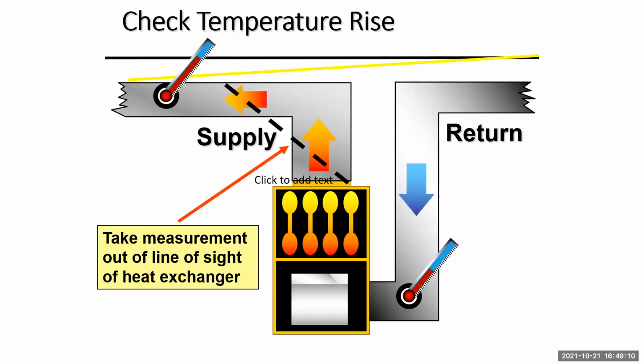Temperature rise. This is critical. If you guys call us and you're having problems, we're going to ask your temperature rise. That and static pressure, and we'll touch on that in a minute. But those are kind of like your entry blood pressures into the emergency room. You don't ever get to go to the ER without them taking your blood pressure, your temperature, all that good jazz. Same thing with us. You don't get to talk to us until you take your blood pressure, AKA temperature rise and static.